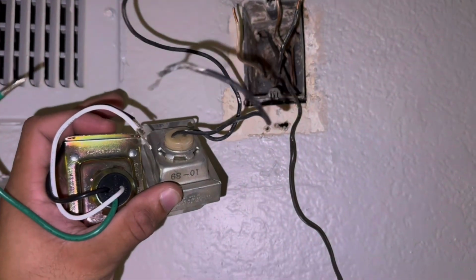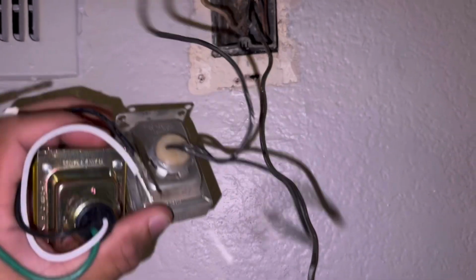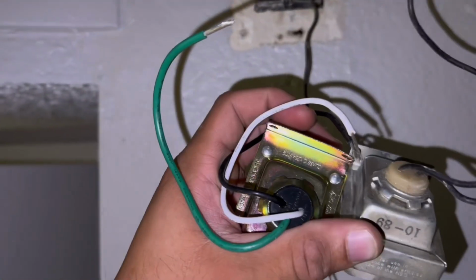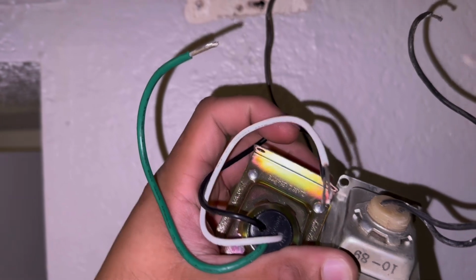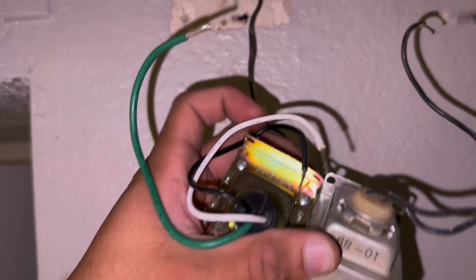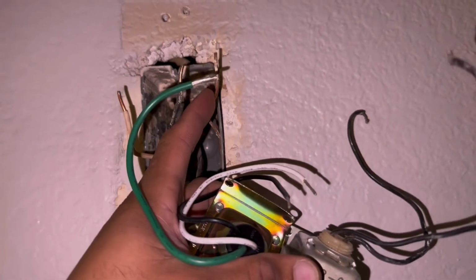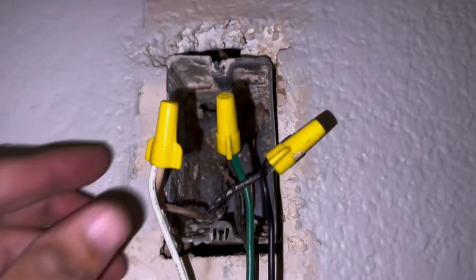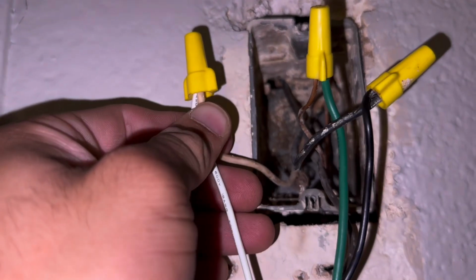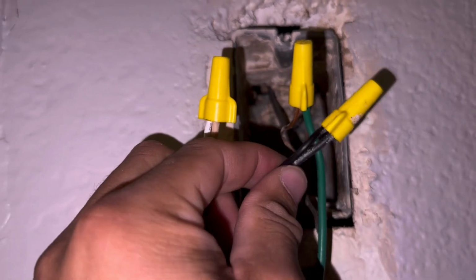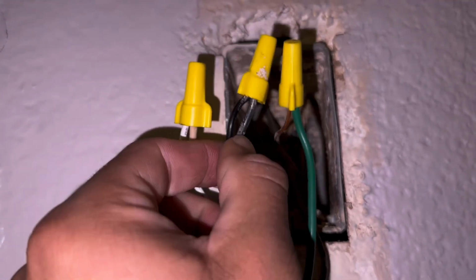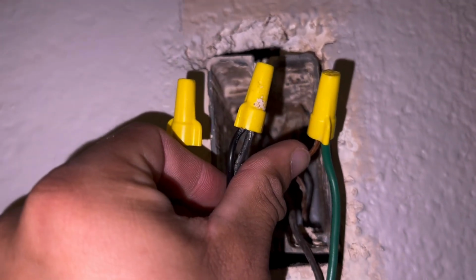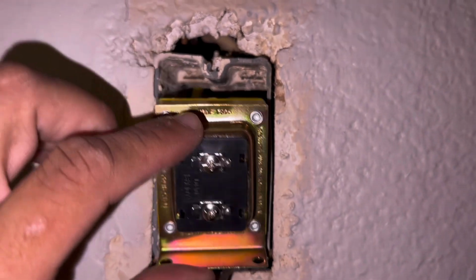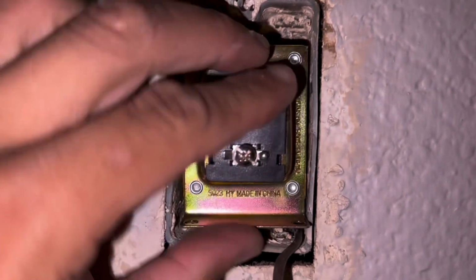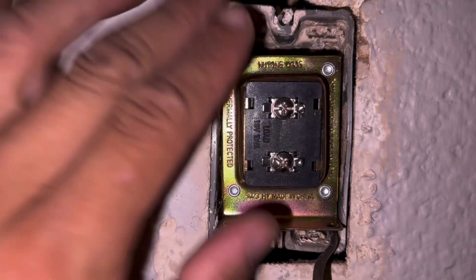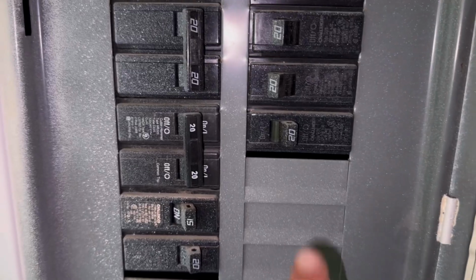Here we have the new transformer that we're going to connect. The old one had 2 wires. On this new one, we have 3. The difference is we have a ground wire, which is the green one, and we're going to connect that to our ground here. Here we've connected our wires, our white leads here. This is my common. The black to black, this is my hot. And then here, as I said, this is my ground. Now that I have my wires, I push them back in, and I'm going to sit my transformer right here inside the box. We'll turn the breaker back on.